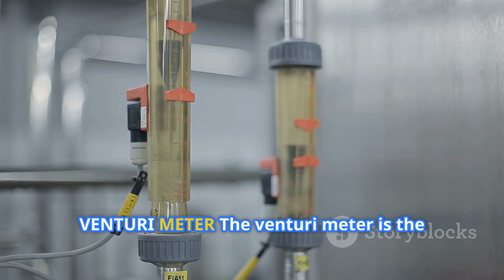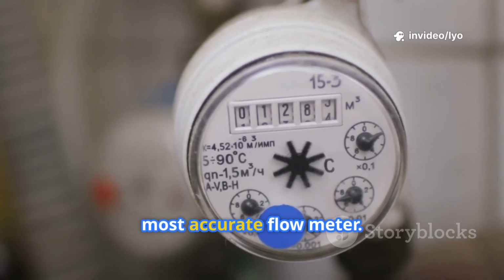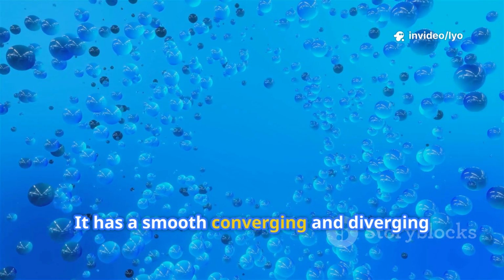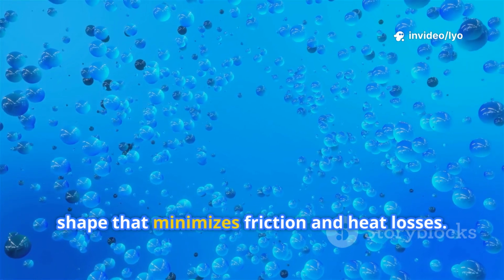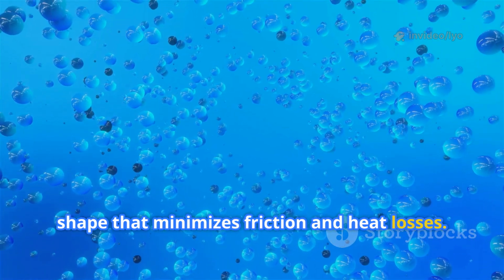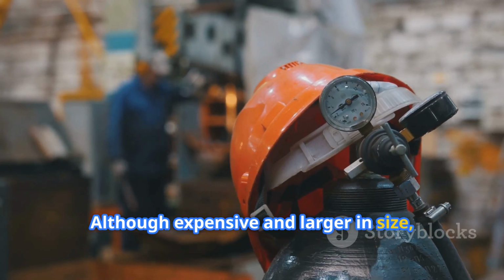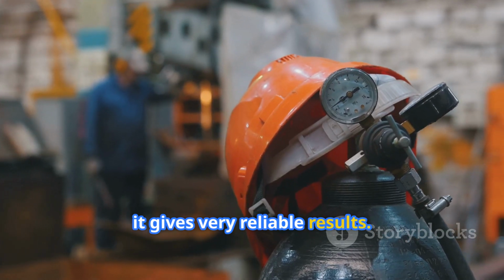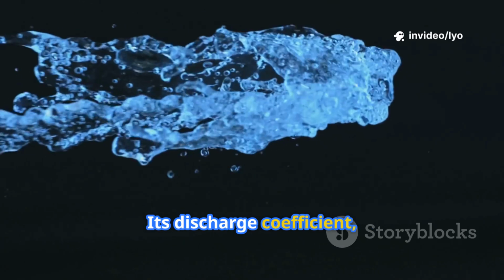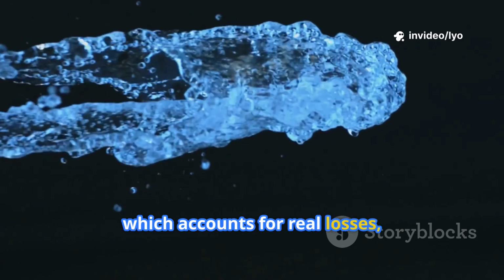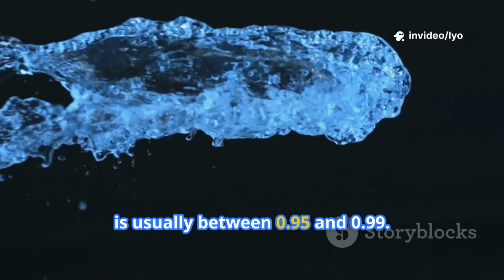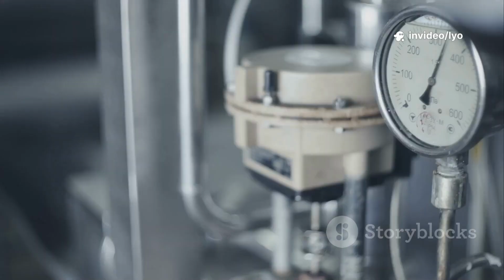Venturi meter. The Venturi meter is the most accurate flow meter. It has a smooth, converging and diverging shape that minimizes friction and heat losses. Although expensive and larger in size, it gives very reliable results. Its discharge coefficient, which accounts for real losses, is usually between 0.95 and 0.99.